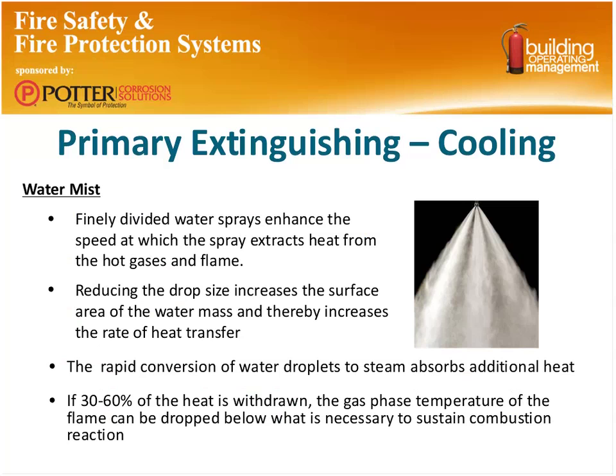How does a water mist system fight a fire? Well, it works on the same principle. It's just by making those droplets smaller, in a lot of cases we can actually suppress a fire, one, with minimal water output, and two, by having a smaller droplet. What we can actually do is that drop's going to flash to steam a lot faster, and it's going to absorb energy. By absorbing energy, we're taking away one of those elements. We're taking away that heat. We're attenuating it. Also, the fact that these small droplets have a tendency to float.